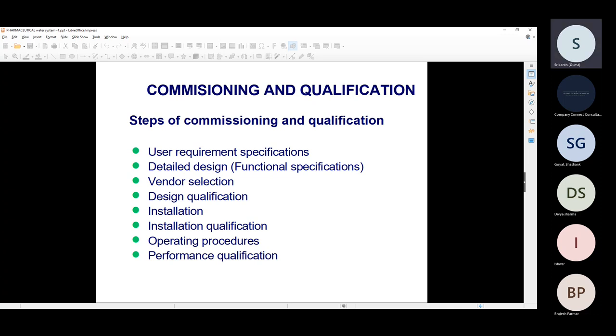DQ in the sense, if I specify I want 4 meter cube per hour RO/DI, then in the design qualification the vendor should give us that same design, or even if it varies, if there is any variation in the DQ, we have to raise a URS deviation request. So URS is our requirement, and DQ is what the vendor is giving us. After the DQ, we have to cross-check what our URS is saying against what the DQ is saying.